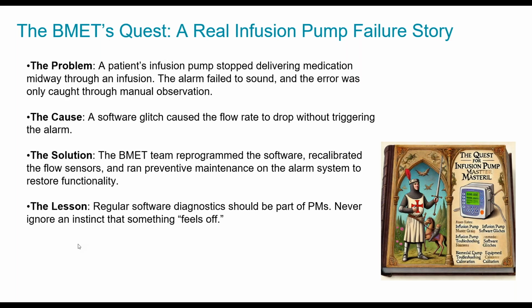And actually, you just reminded me of something I should probably tell this audience. Gut checks aren't always a good thing, right? Making an assumption before you check it out, as Robert said, and evaluate the technical aspects of the pump—you can rule in or rule out a lot of things with the technical aspects. But to use a gut check in a bad way, like saying, well, it must have been operator error, be very, very careful. It's political, of course, but be very careful about creating or instilling a culture where the assumption is it was somebody else's fault. That can be a bad use of the gut check.